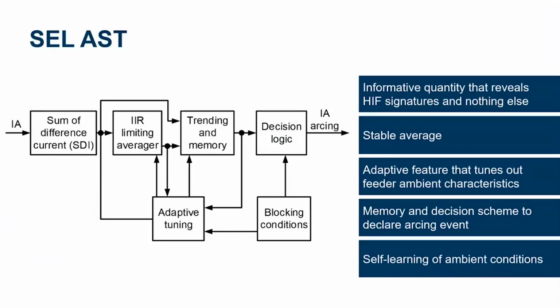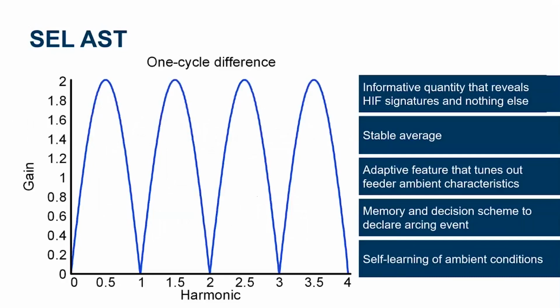The way that we're doing this is by using what's called a sum of difference currents. We're taking the time slotted currents, doing 32 samples per cycle, and we're going to subtract the sample that we take now from the sample one cycle ago, and then sum all of those differences together. So a sum of difference. What you get from this is this frequency response. We're adding some gain here, and we end up with this overall frequency response for the sum of difference currents, that is the input into our AST algorithm.